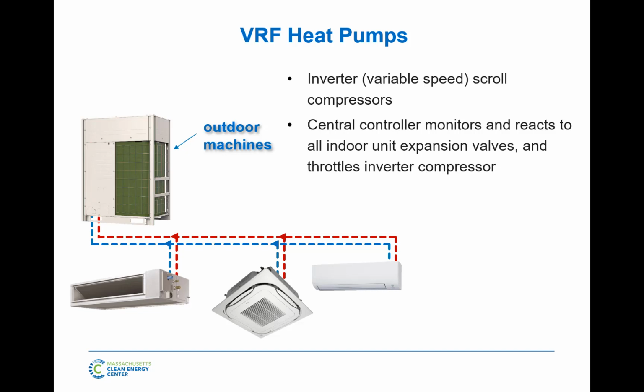Same for the fans. The condenser fans are all variable speed fans. If you've ever looked at a condenser on the roof, you can see the top of the fans rolling, the regular stamped sheet metal units that are quite loud. This is different. These are all polymer aerodynamic fans. They're extremely quiet, and they're all variable speed. So this side of the heat exchanger, the fans, the outside air, also varies up and down based on all sorts of things. What's my load? What's my outside air temperature? Long story short, the variable speed compressor, the variable speed fans, the variable expansion valves that open and close based on demand is what makes these systems perform at part load conditions.